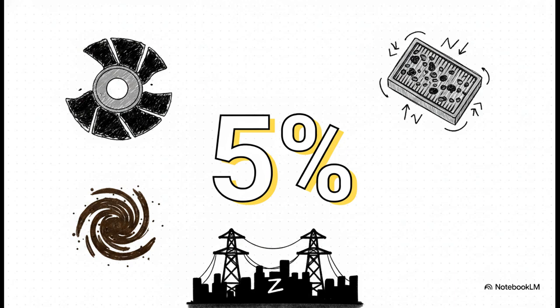As blades naturally erode and combustion deposits build up, you face a rule of thumb 5% power loss simply from operating what we call a dirty engine. Your lube oil gets less efficient, air filters clog up, and the aerodynamic efficiency of those turbine blades degrades over time. If you don't account for this 5% dirty engine penalty during the design phase, well, you're going to face some severe embarrassments and likely blackouts once the machine is actually in service.